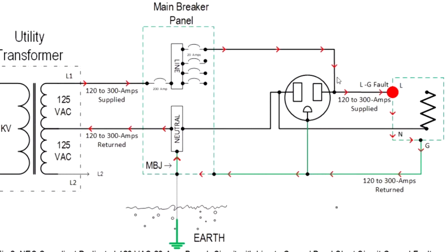Now, notice what ground is actually physically doing at this time. Notice that Earth is doing something, but it's not in the fault path. Everyone see that? Earth is not in the fault path, and it's done intentionally that way. You cannot use Earth as a conductor.